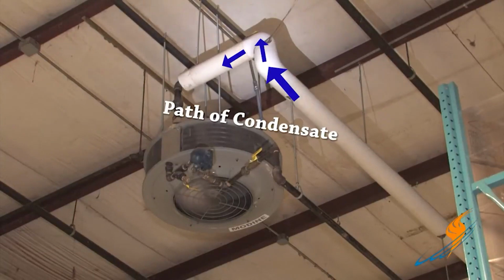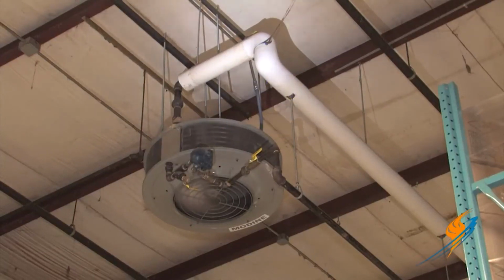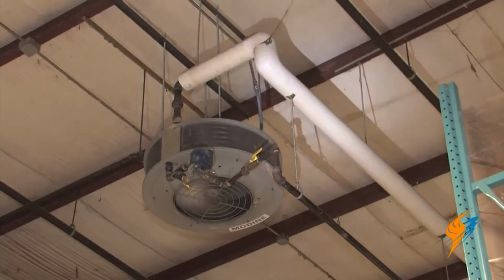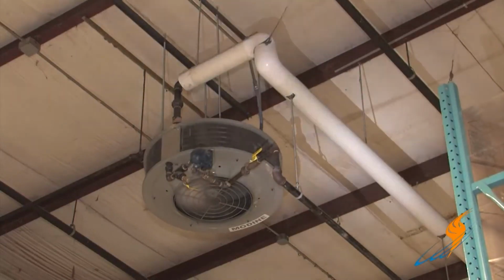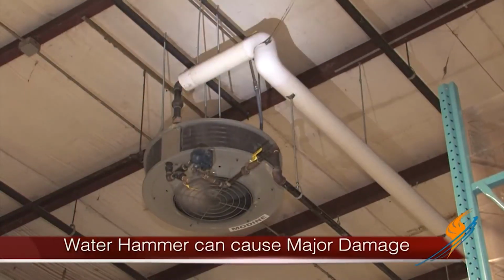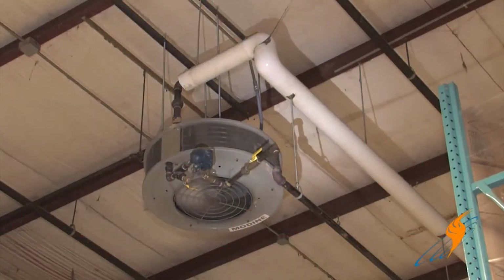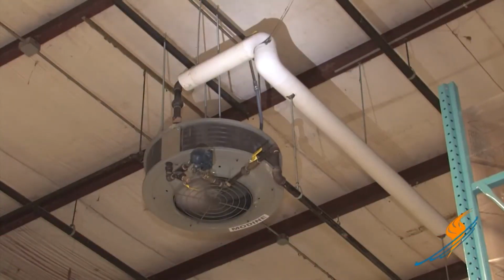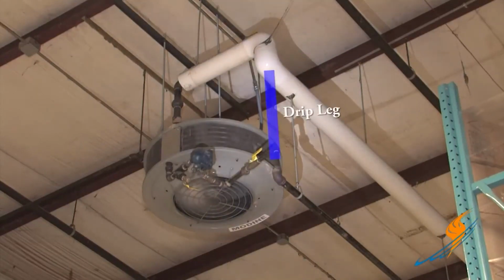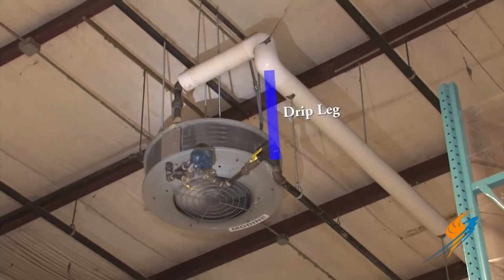And of course, anytime we try to get condensate to flow up, we're working against gravity, and we can generate steam or water hammer in this line. So it's really important when we've got a terminal unit or the last unit in a run that we have a drip leg at this first elbow, which should have its own trap and pipe it down into the outlet of the trap on the unit.